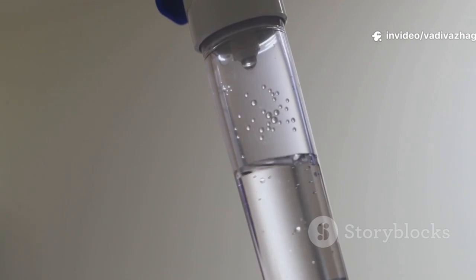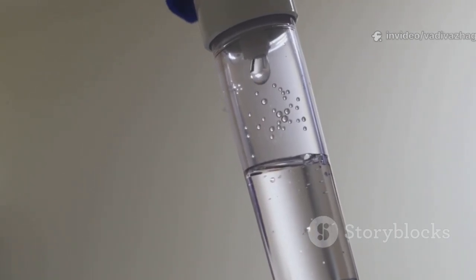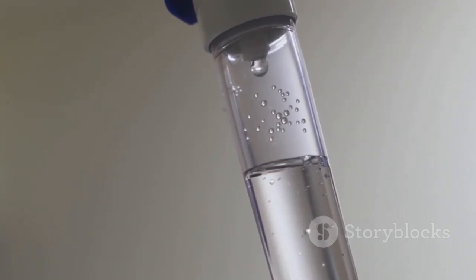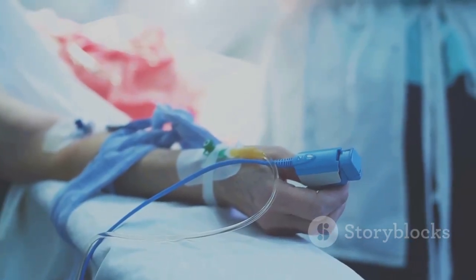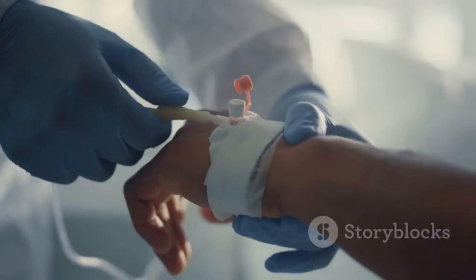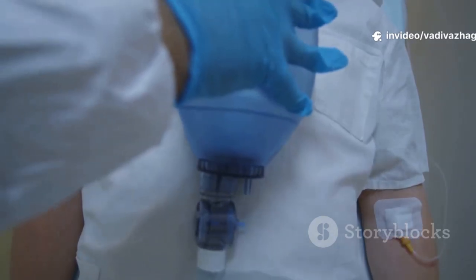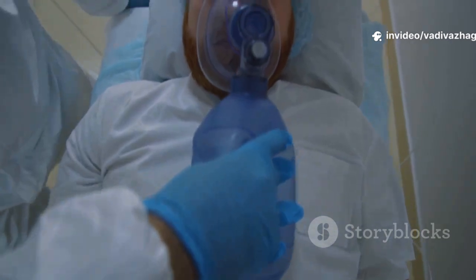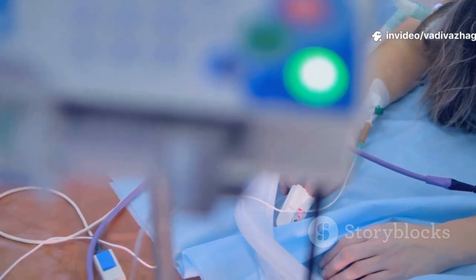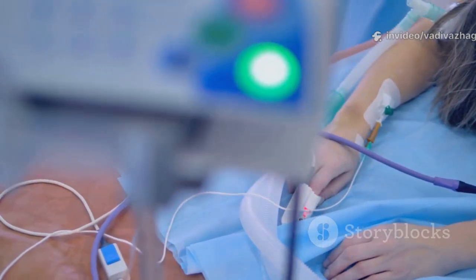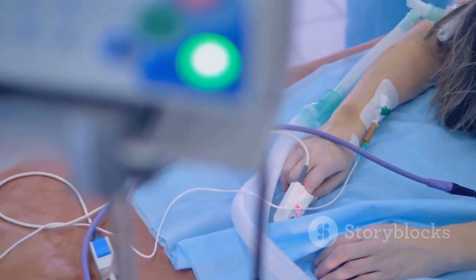Now, prepping the system. I check that all tubing and the transducer are primed with flush solution, no air bubbles. Then, I find the stopcock closest to the transducer. Time to open the system to air. I turn the stopcock off to the patient and open it to the air. This exposes the transducer to atmospheric pressure. Some systems have a cap or a special port for this.